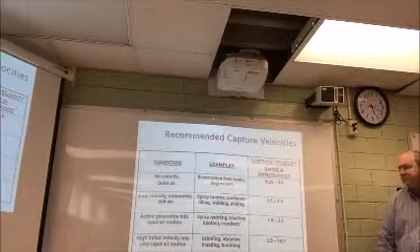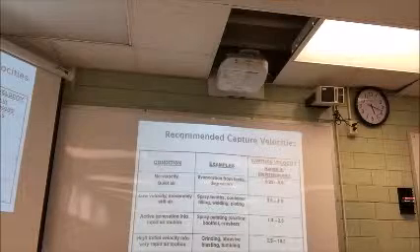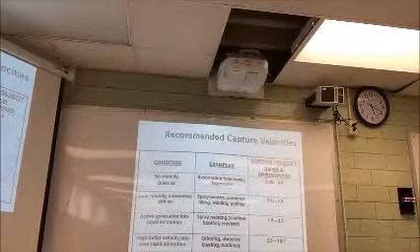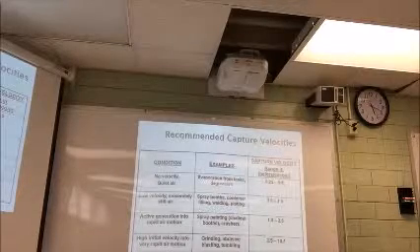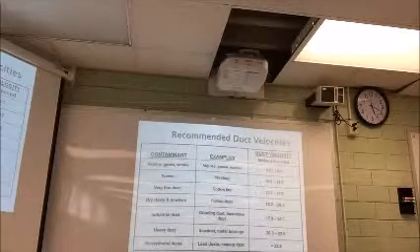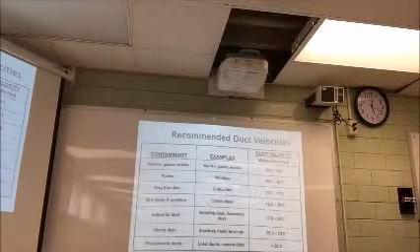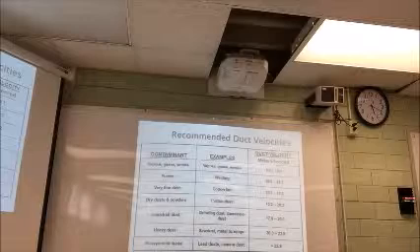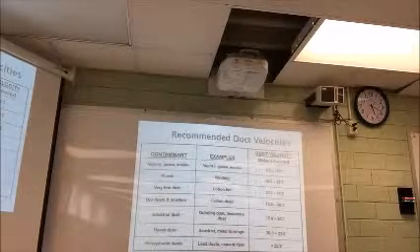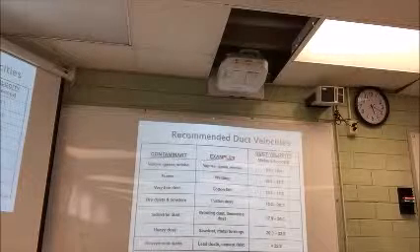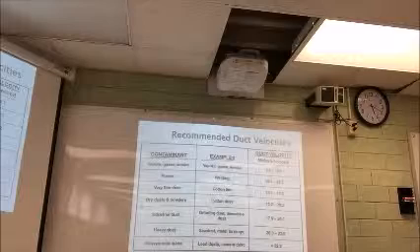Here are also some recommended capture velocities. Again, this is out of the ventilation manual. You guys can just kind of look at those and say, hey, that's something that we need to discuss and know. This shouldn't surprise you. Just out of curiosity, you guys did this, I think, last week. What is 10 meters per second? How many feet per second, or feet per minute, is that? What do you guys think?